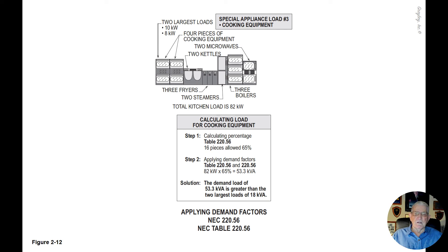Now we're ready to apply a demand factor for this type of equipment that may be in a restaurant or a cafeteria. To calculate the load for the cooking equipment, we apply Step 1 and use Table 220.56 to obtain our percentage. With 16 pieces of cooking equipment, Table 220.56 allows a 65% demand factor.